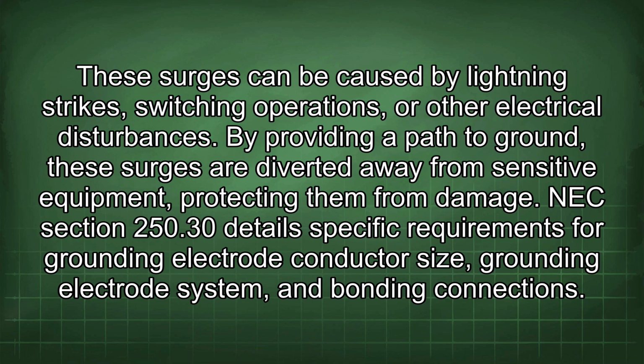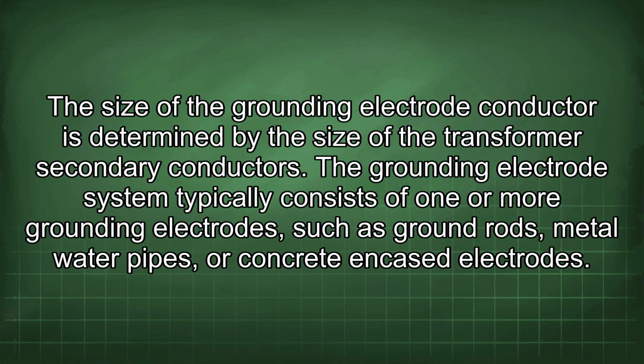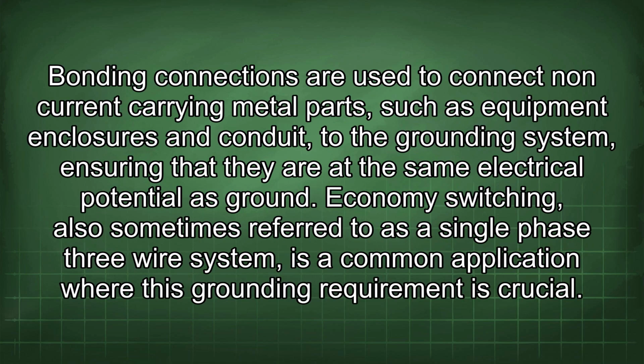NEC section 250.30 details specific requirements for grounding electrode conductor size, grounding electrode system, and bonding connections. The size of the grounding electrode conductor is determined by the size of the transformer secondary conductors. The grounding electrode system typically consists of one or more grounding electrodes, such as ground rods, metal water pipes, or concrete encased electrodes. Bonding connections are used to connect non-current carrying metal parts, such as equipment enclosures and conduit, to the grounding system, ensuring that they are at the same electrical potential as ground.